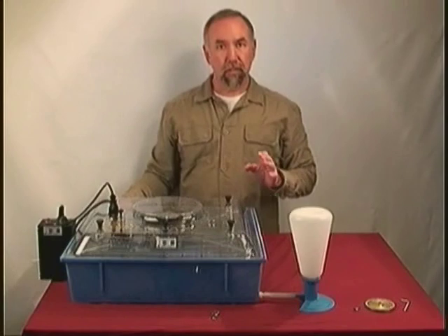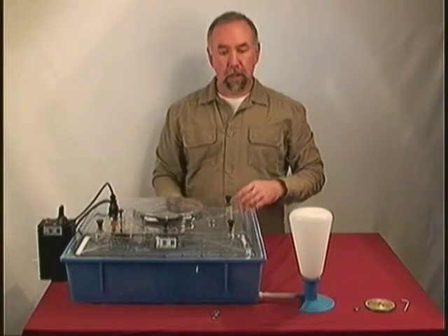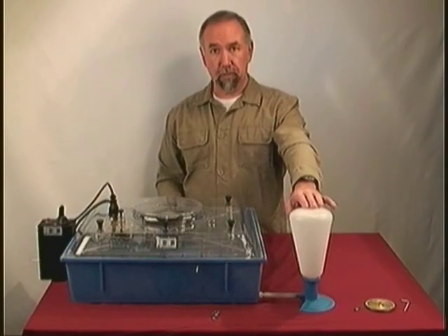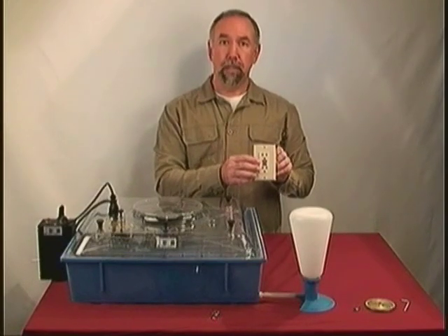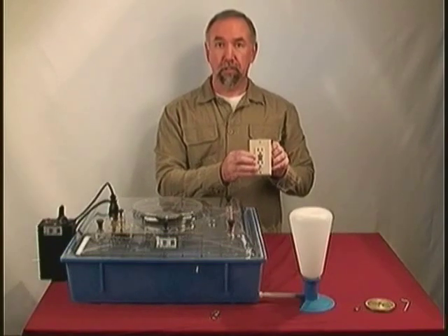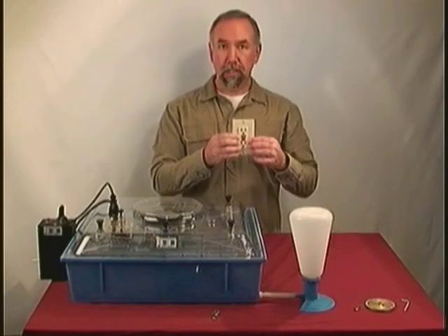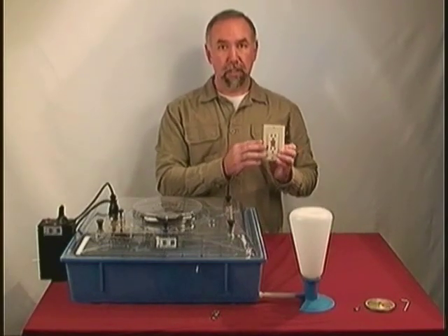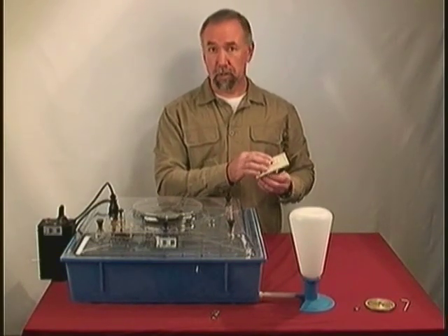Because this is a 200 watt unit and you're dealing with water in the incubator and will be handling water when filling the reservoir, I recommend that you plug it into a ground fault circuit interrupt type plug. Look for that — it should already exist if you're doing this in a kitchen or a lab environment where there are work tables and sinks nearby. You want to make sure you have ground fault circuit interrupt. This will prevent receiving electrical shock from the system if you are wet and there's some kind of short or problem with it.